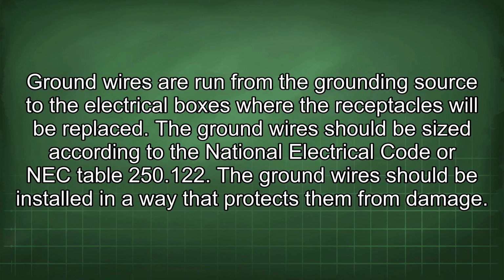Ground wires are run from the grounding source to the electrical boxes where the receptacles will be replaced. The ground wires should be sized according to the National Electrical Code, or NEC, Table 250.122. The ground wires should be installed in a way that protects them from damage.